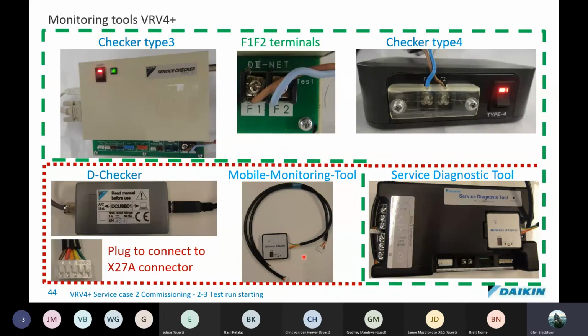Monitoring tools during the test run. Okay, so let's have a look. Different monitoring tools that are available. The first type is the Service Checker 3. This is the older of the service checkers. And then we have the Service Checker 4, which you'll see a lot of the Daikin technicians now carry with them, a smaller box, but easier to operate as well. Just remember that these devices connect to the F1, F2, DIII-NET. Okay, and they connect on the F1, F2 outdoor.